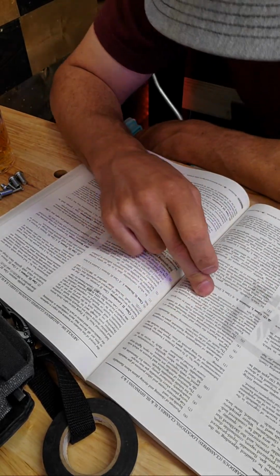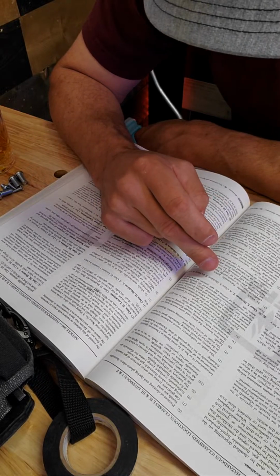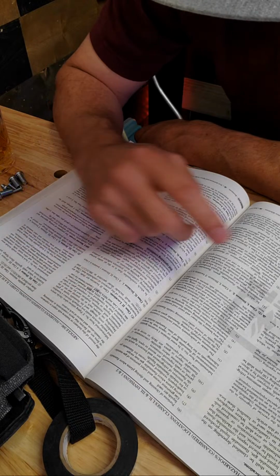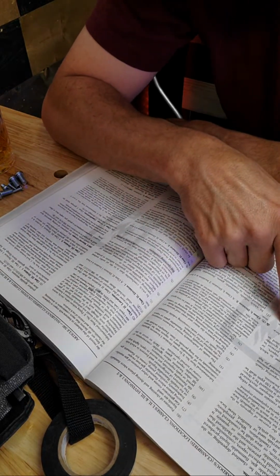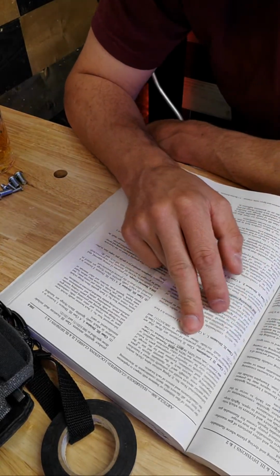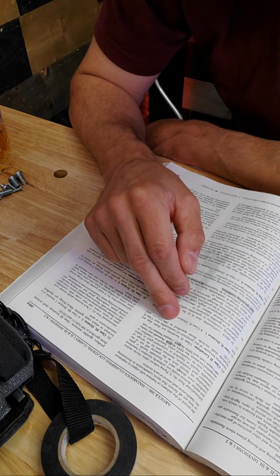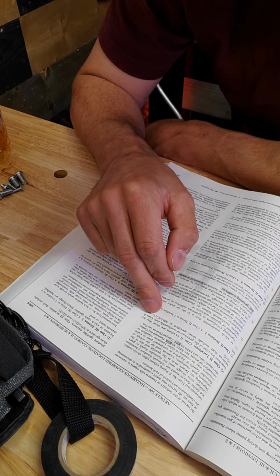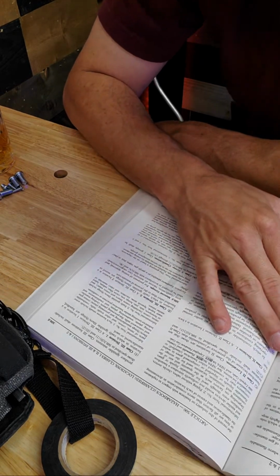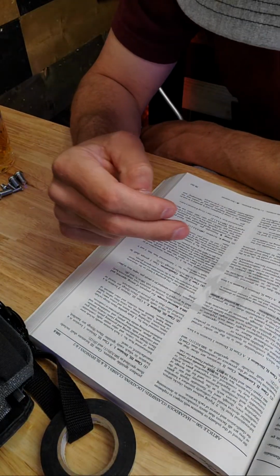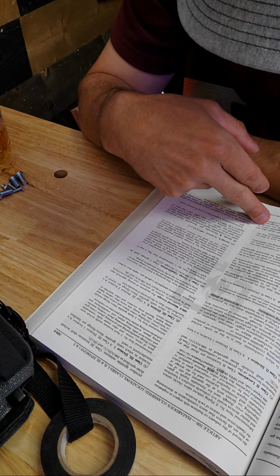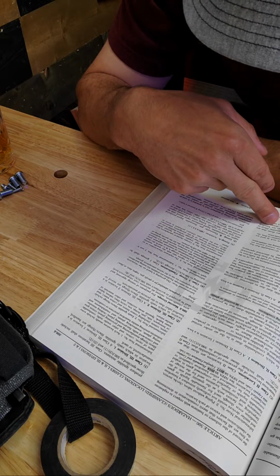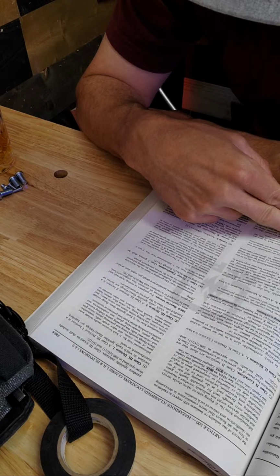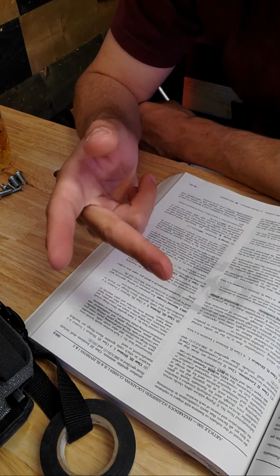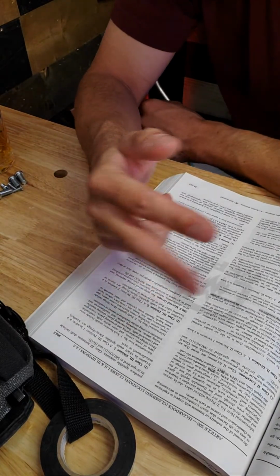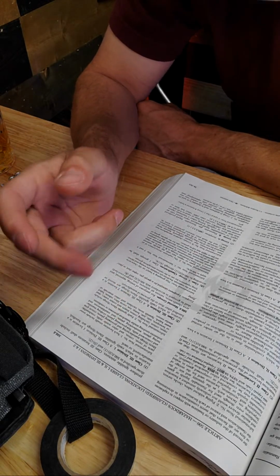A Class 1 Division 2, the division's just going to be a little bit more strict. And so we know Class 1 is going to be ignitable, flammable gases. Class 2 is going to be hazardous because of the presence of combustible dust, which is where a granary would be. So if we look at probably a Class 2, and then if we look at a Class 3, that's going to be hazardous because of the presence of easily ignitable fibers, or where materials producing combustible flyings are handled. So that would be like a sawmill or something like that. Even your workshop could be a Class 2, technically speaking, if you had enough flying small wood dust, things like that.